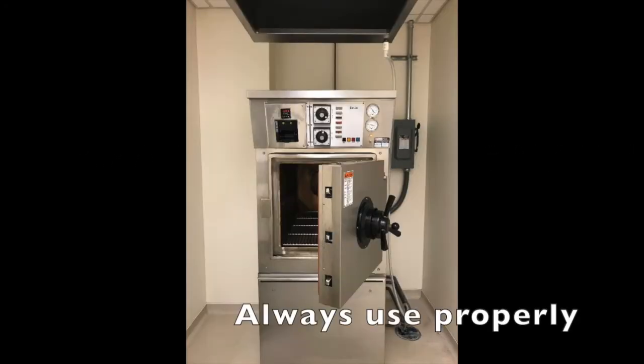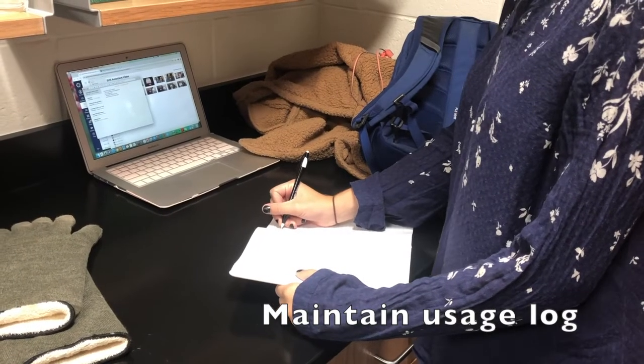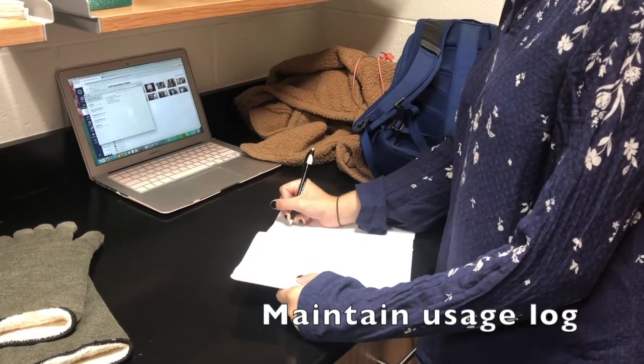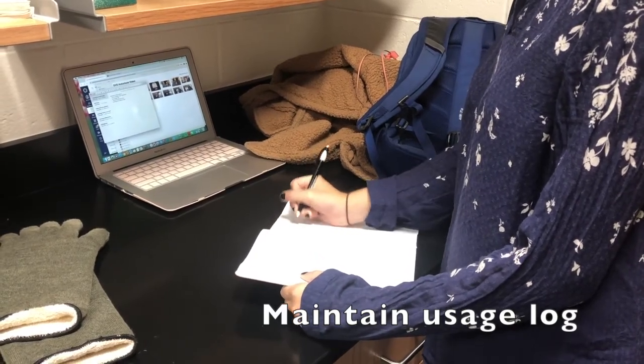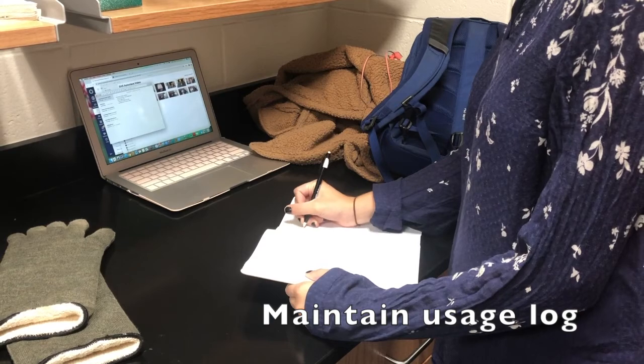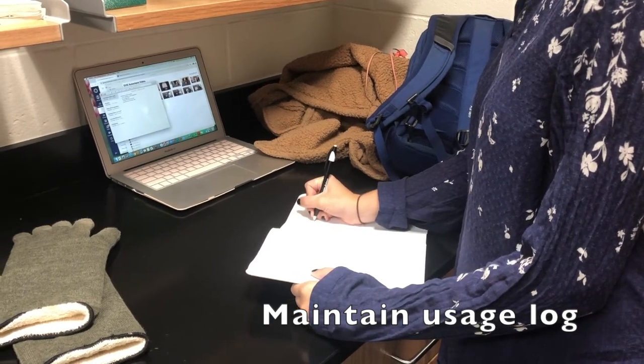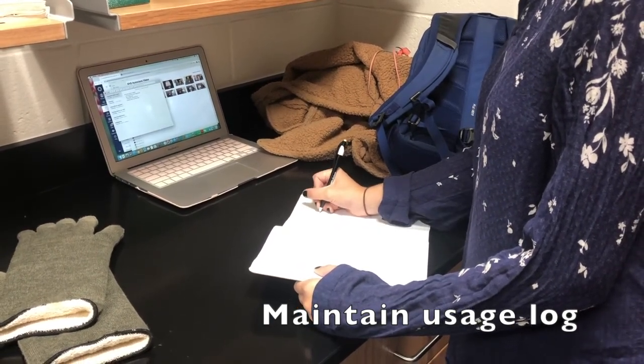First of all, you need to make sure to always use the autoclave properly by following the steps mentioned earlier in the video. You also need to maintain an autoclave usage log every time an autoclave cycle is run. The log should include the date and time of the cycle, the operator and their contact information, what was autoclaved, and the temperature, pressure, and time length of the cycle.